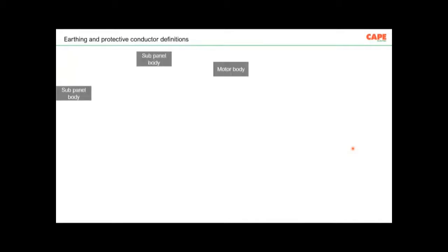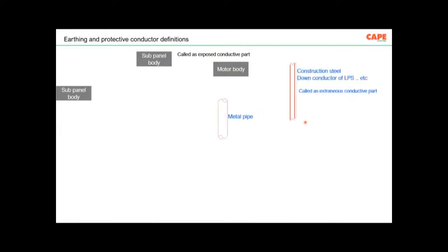Now, how to do earthing in a building? What kind of connections are required? What are the names? What are the terms used? In your building, you will have exposed conductive parts such as panel board body, motor body. Exposed conductive parts are applicable for class 1 equipment, not for class 2 equipment. Then your installation also will have extraneous conductive parts, such as the construction steel, metal pipe, metal handrail, sometimes aluminum facade, the frame of aluminum facade, and all these are called extraneous conductive parts.